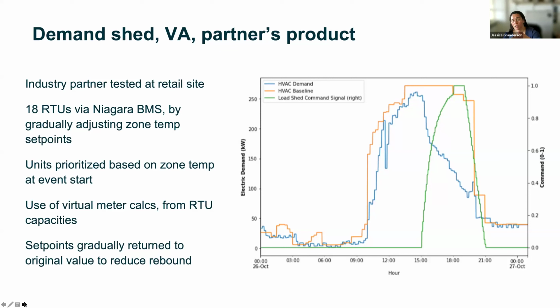The baseline is shown in orange. That's what the HVAC consumption of these 18 units would have been in the absence of any demand flexibility. The blue shows you the shed starting at about 1500 hours. The green is the shed command signal across this set of 18 units. So you can see that more and more units are brought in as more and more load is shed, and around 2100 this test concluded.